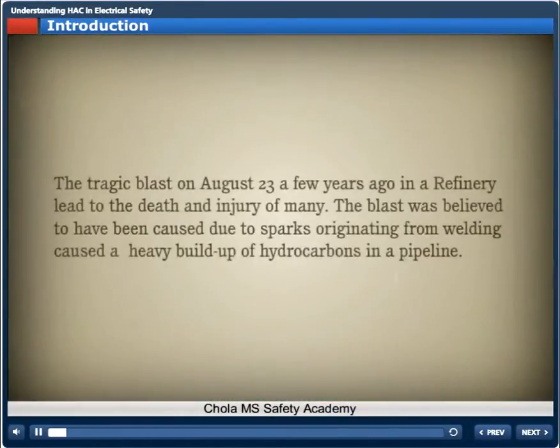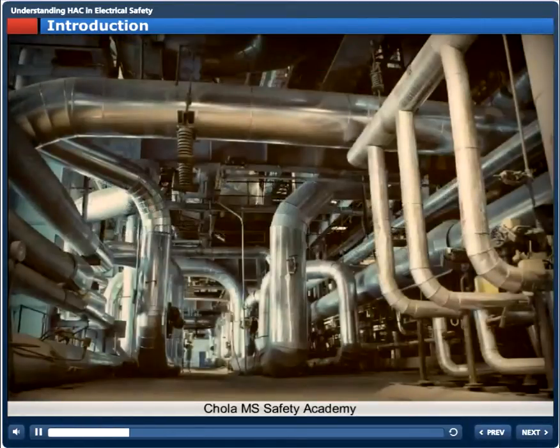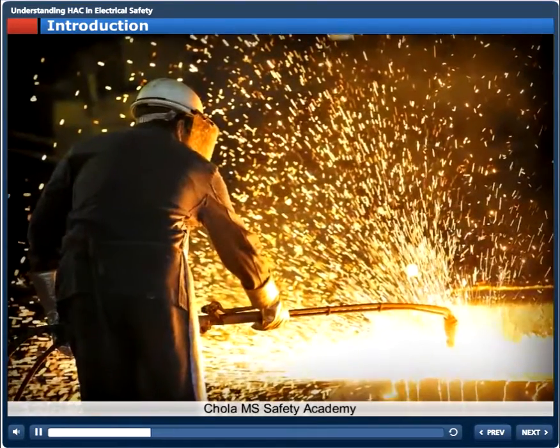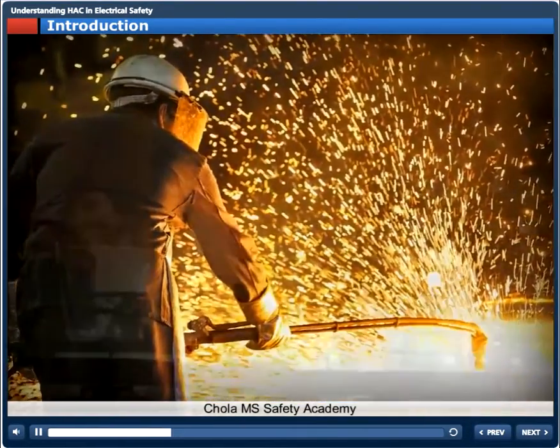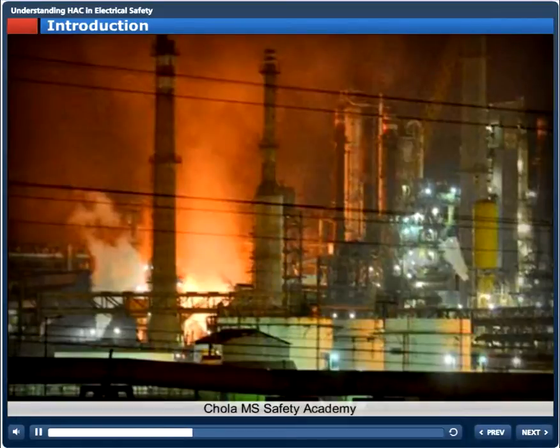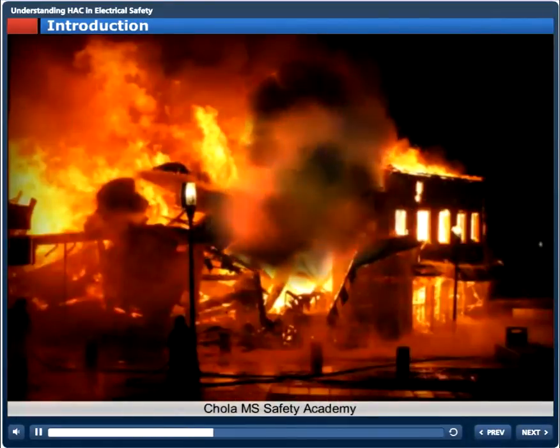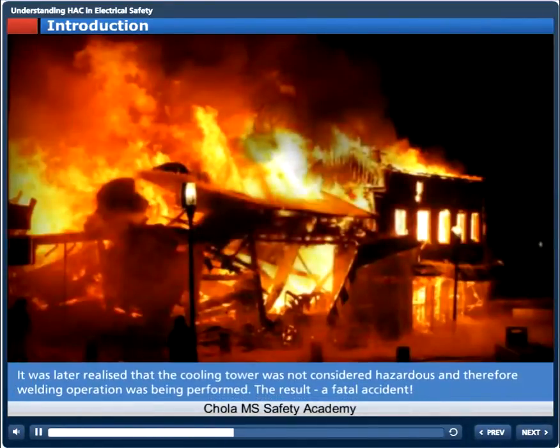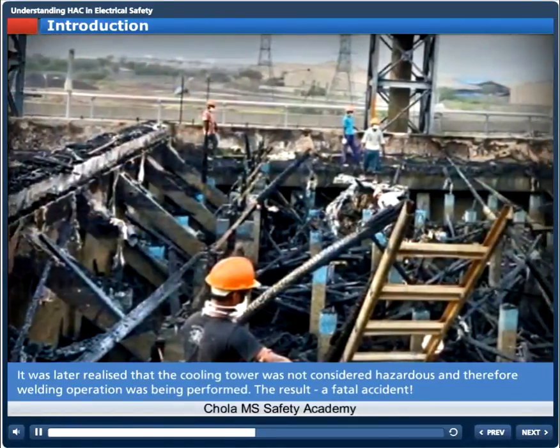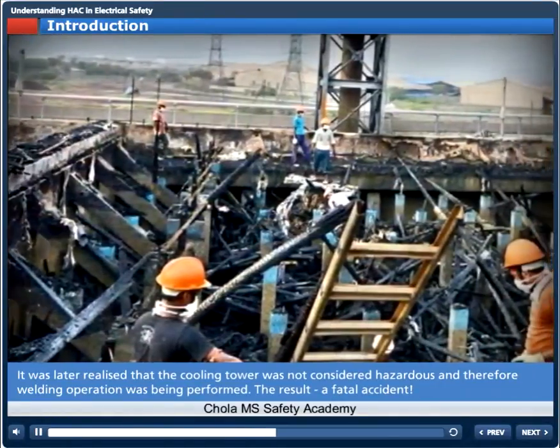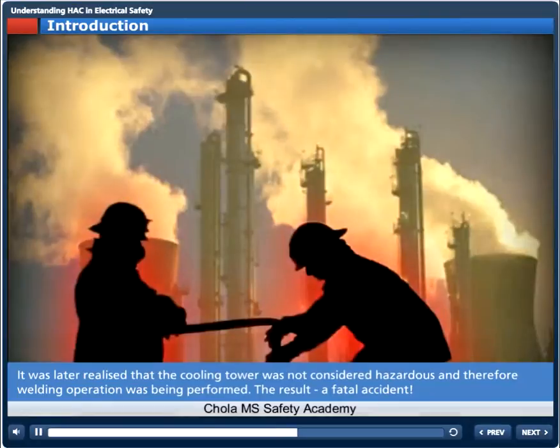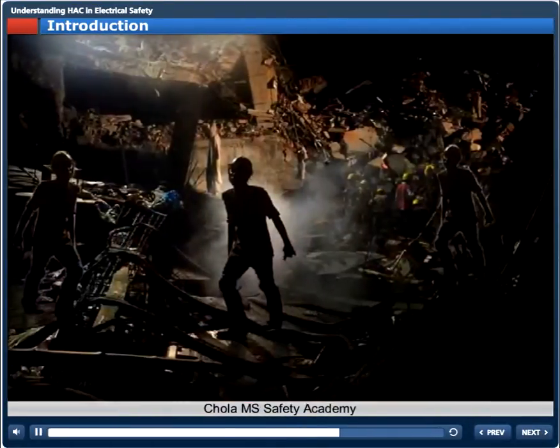The world-famous blast on August 23, which was believed to have been caused due to sparks originating from welding, caused a heavy buildup of hydrocarbons in a pipeline. This led to the blast and collapse of the cooling tower. It was later realized that the cooling tower was not considered hazardous, and therefore welding operation was being performed. The result, a fatal accident.